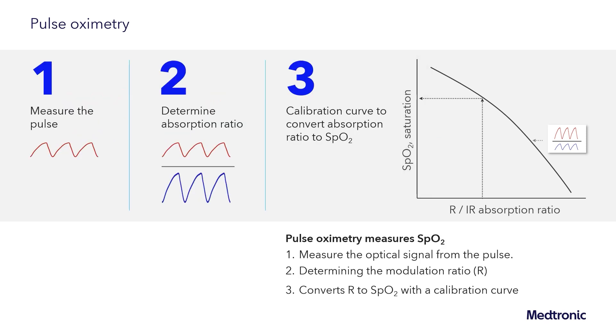With that, we have covered three important aspects of pulse oximetry. First, you have to measure the pulse. Once you measure the pulse, you are able to determine the absorption ratio of the red and infrared LEDs. From that absorption ratio, you are then able to convert to an SpO2, or a saturation.